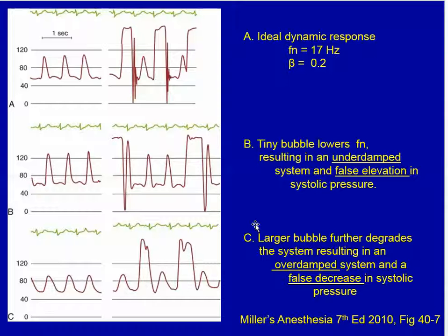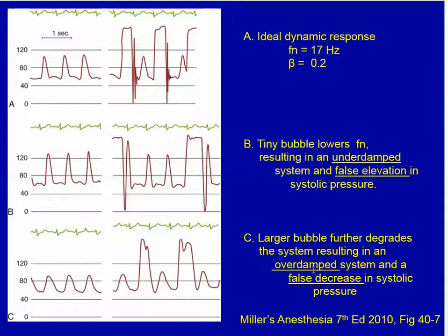This shows the effect of bubbles. Starting from an ideal tracing with a natural frequency of 17 and a damping coefficient of 0.2, adding a tiny bubble results in an under-damped system which lowers the natural frequency and causes false elevation of the systolic pressure. On the other hand, putting a large bubble in the system results in an over-damped system and a false decline in the systolic pressure.